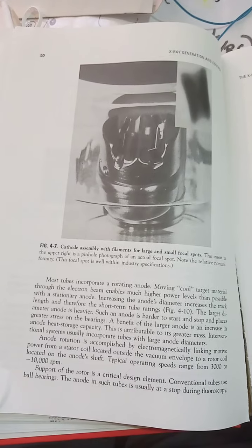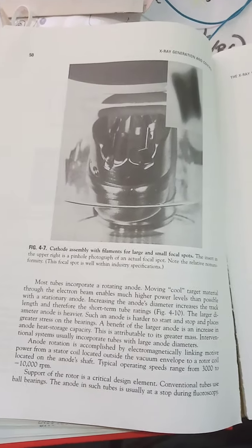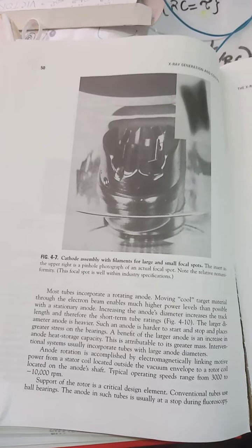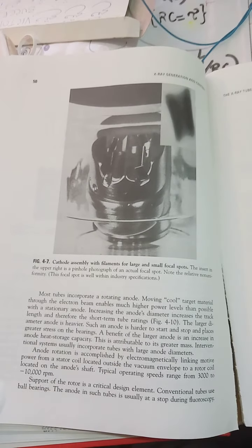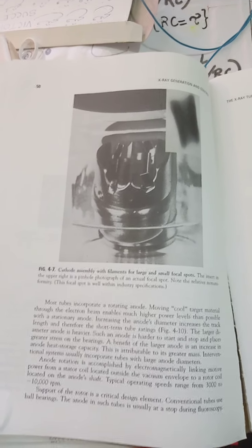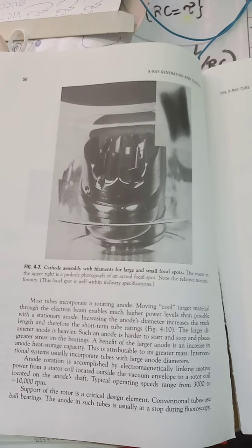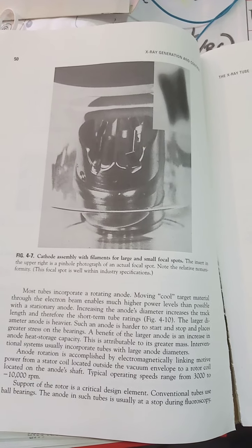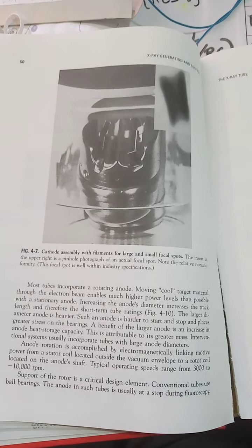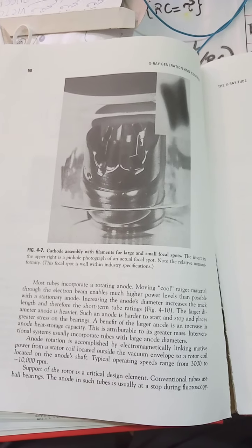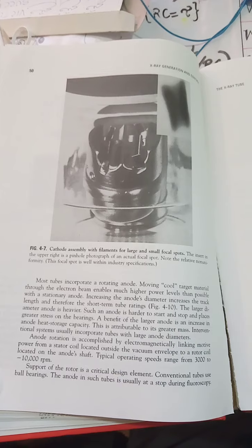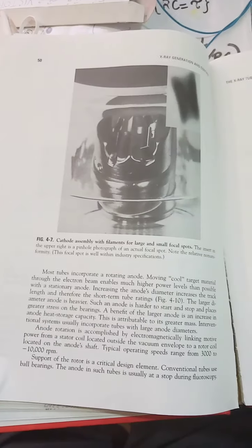Here it's talking about the rotating anode, how it increases the efficacy of X-ray production and focus on the target. Moving cool target material through the electron beam enables much higher power levels than possible with a stationary anode, because the stationary anode may get heated far more quickly. So increasing the anode's diametric dimensions increases the track length, and therefore the short-term tube ratings. Anode rotation is accomplished by electromagnetic linkage, and the motive power from the stator coil located outside the vacuum envelope to a rotor coil located on the anode's shaft. Typical operating speeds range from 3,000 to 10,000 RPM.